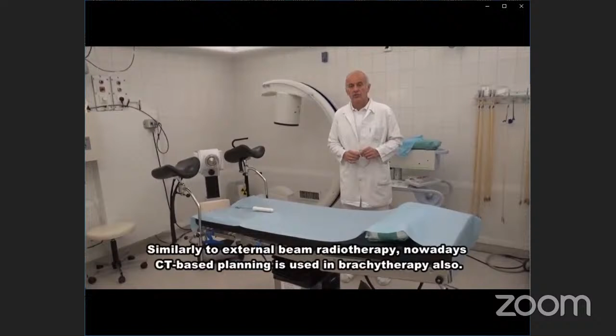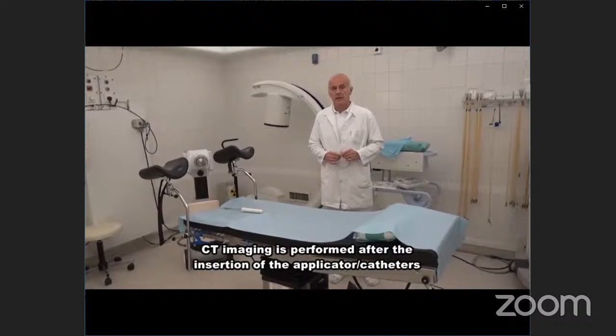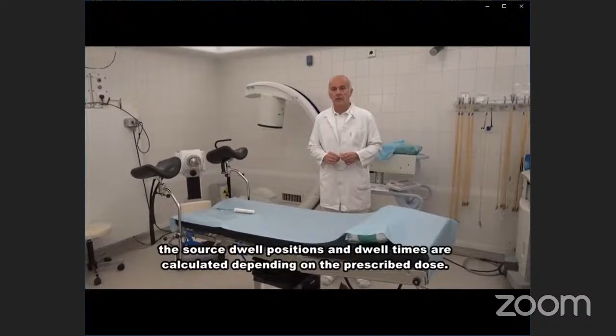A few words about treatment planning. Similarly to external beam radiotherapy, nowadays CT-based planning is used in brachytherapy also. CT imaging is performed after the insertion of the applicators or catheters, which are then reconstructed on the CT images. Target volumes and organs at risk are contoured, and with a special software, the source dwell positions and dwell times are calculated depending on the prescribed dose.